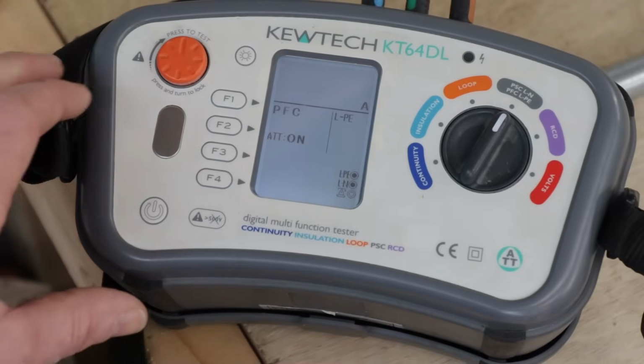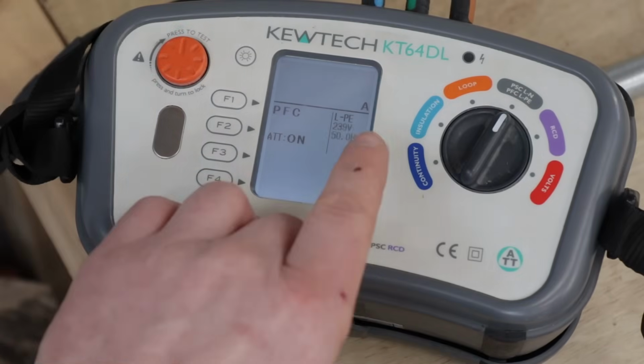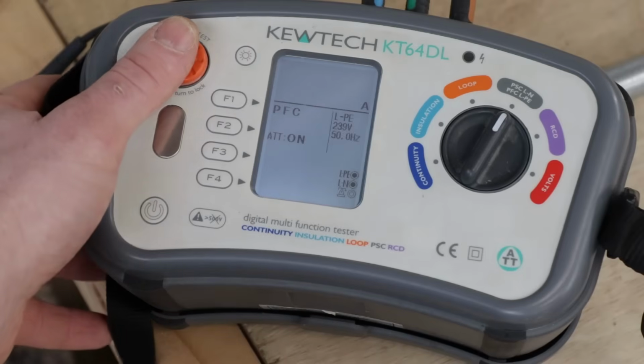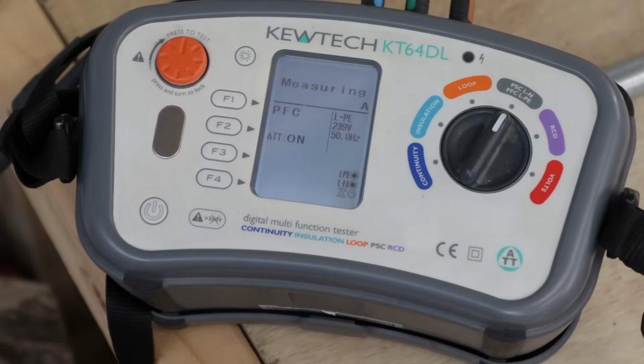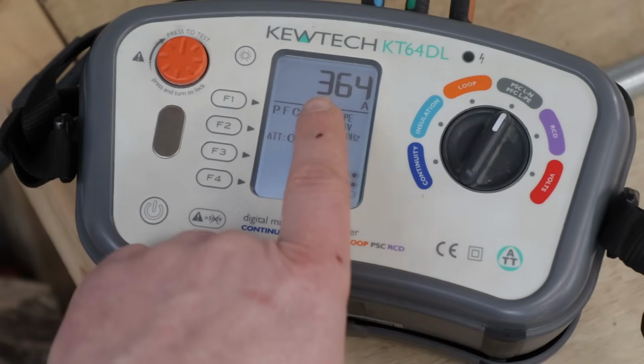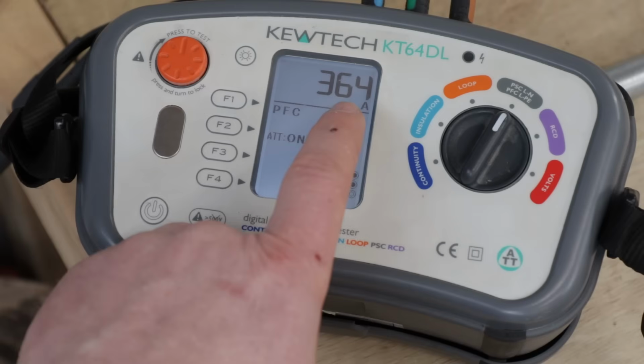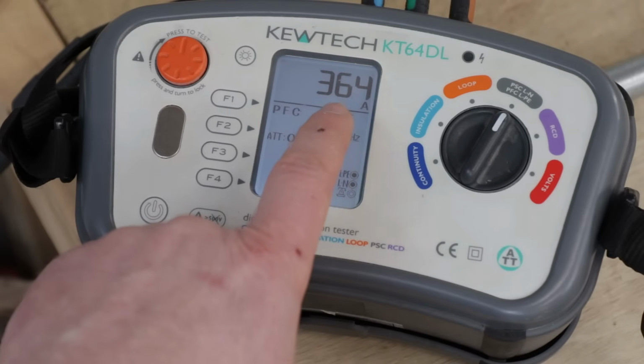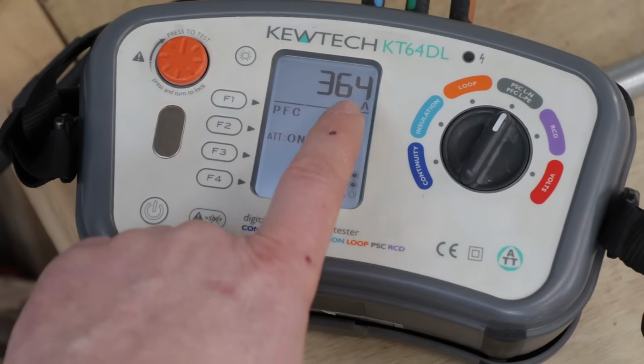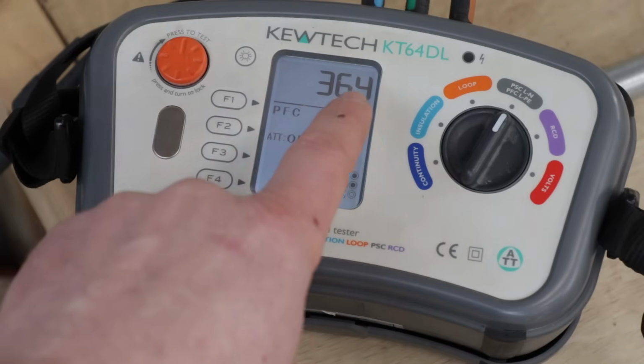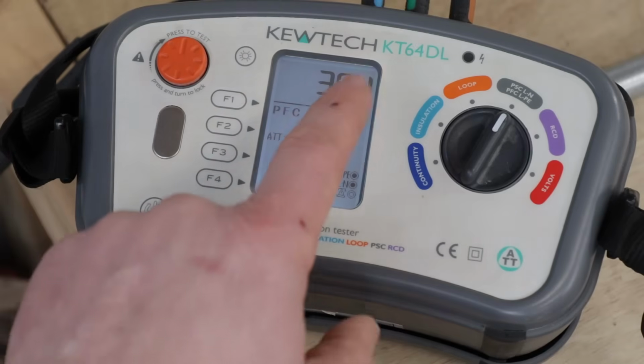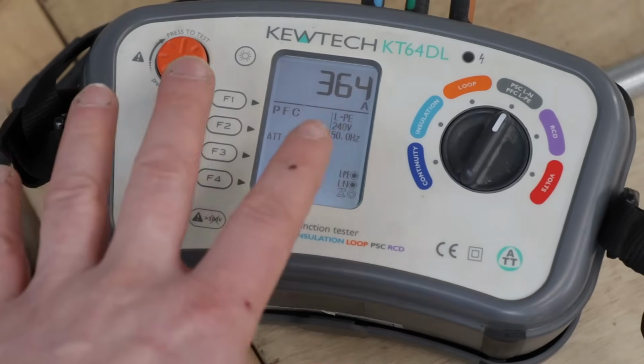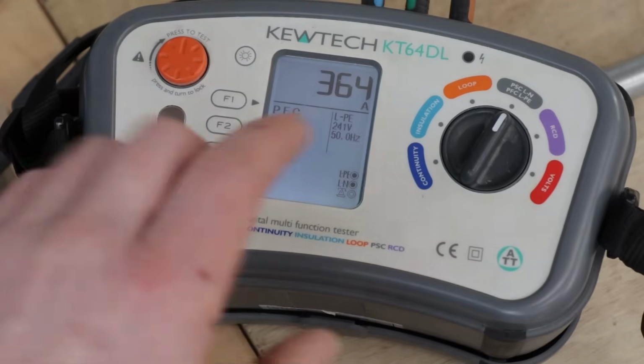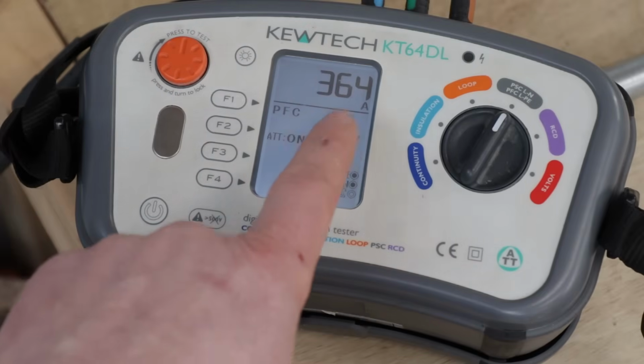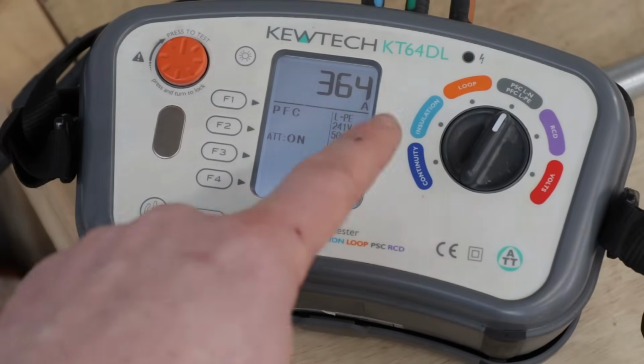So if I switch over to here, this will tell me what current will flow if I was to short out those two cables. So there you go, 364 amps would flow in an instant if I was to short out that live and that earth. So I know that's well over 3 to 5 times the tripping current for a 20 amp MCB. So I know I'm good. That will blow out my MCB if I get a short circuit. However, let's add our extension lead now and do this test again.